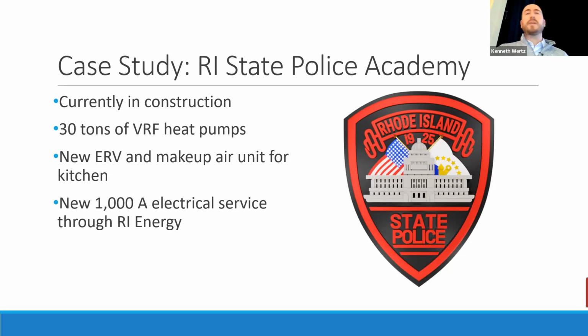That's partly driven by the heat pumps. Partly they had domestic hot water and cooking that was using propane. So the 1,000 amps is meant to cover those being electrified as well. But just for context, talking about a 10,000 square foot building that doesn't have anything too crazy in terms of equipment, they need 1,000 amps. So that gives you some context of what some of these other buildings might need.